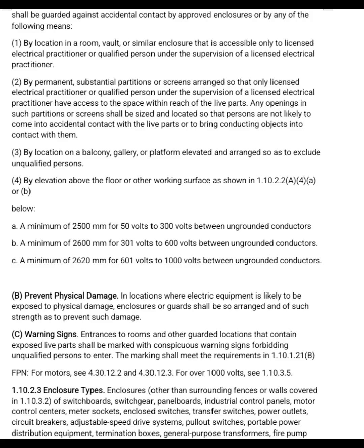B. Prevent physical damage. In locations where the electrical equipment is likely to be exposed to physical damage, enclosures or guards shall be so arranged and of such strength as to prevent such damage. Letter C. Warning signs. Entrances to rooms and other guarded locations that contain exposed live parts shall be marked with conspicuous warning signs forbidding unqualified persons to enter.